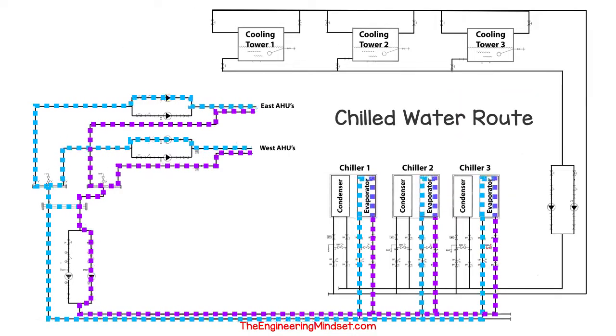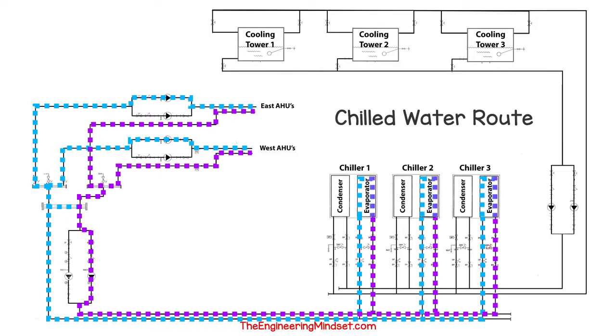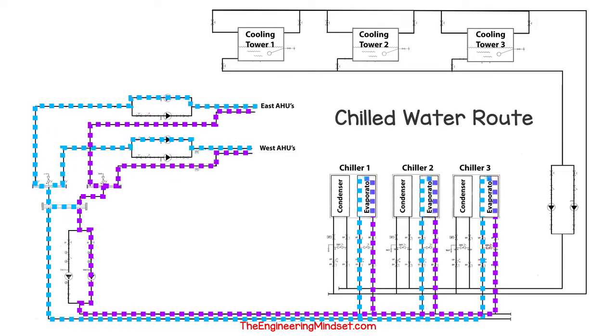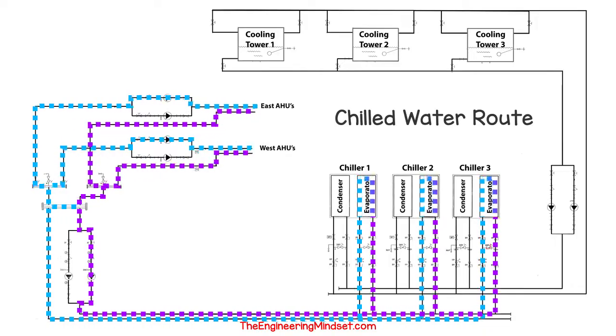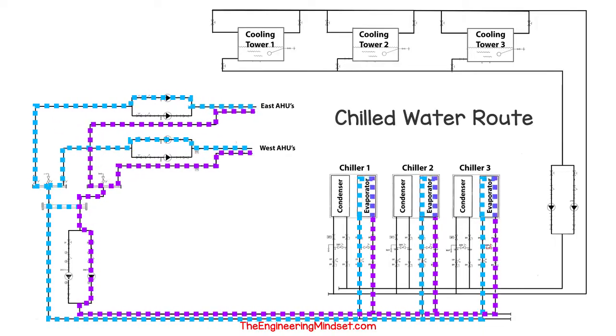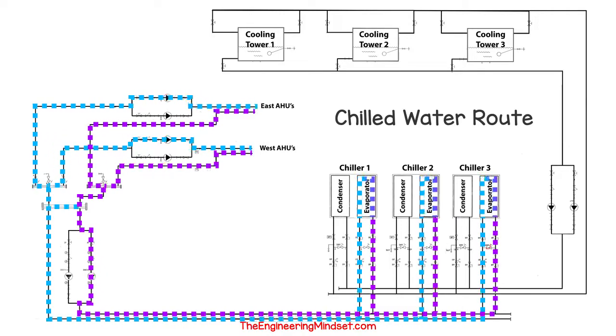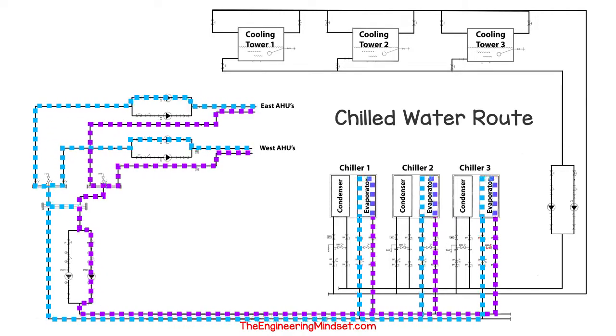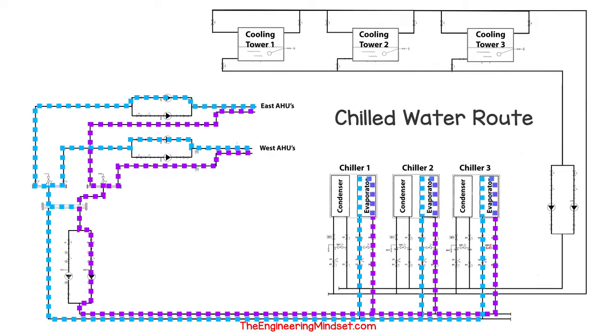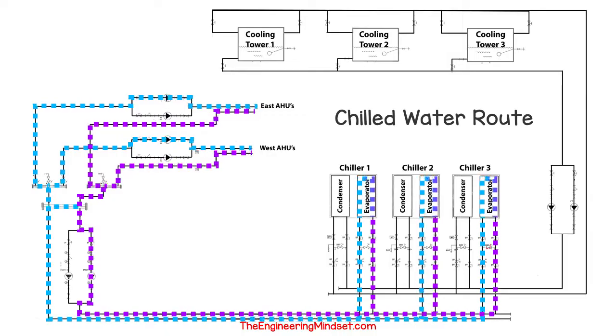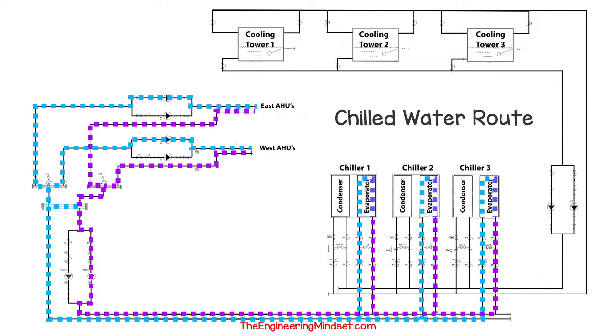This is a simplified version of the actual chilled and condenser water schematic of the building. As you can see, it has three chillers and three cooling towers, and this feeds the AHUs in both the east and the west side of the building. I've only animated the flow path of the chilled water for this example, as that's what we're measuring, although the procedure will be the same if you wanted to measure the condenser water. Note that not all three chillers need to run — this would only occur at maximum demand.